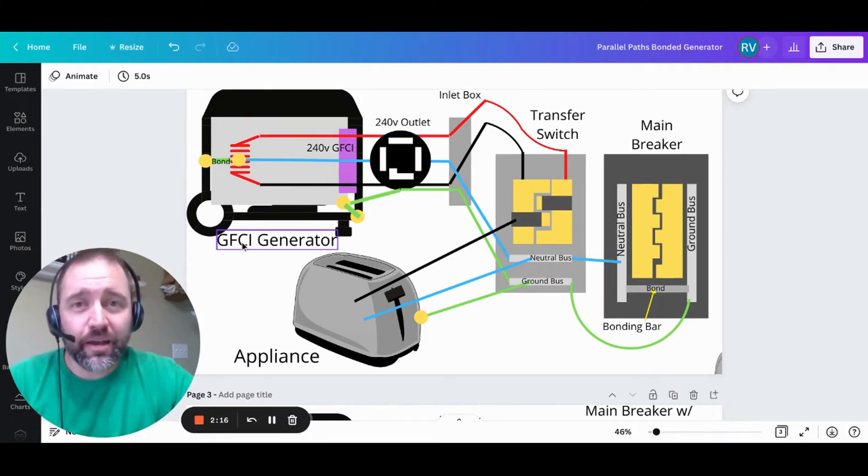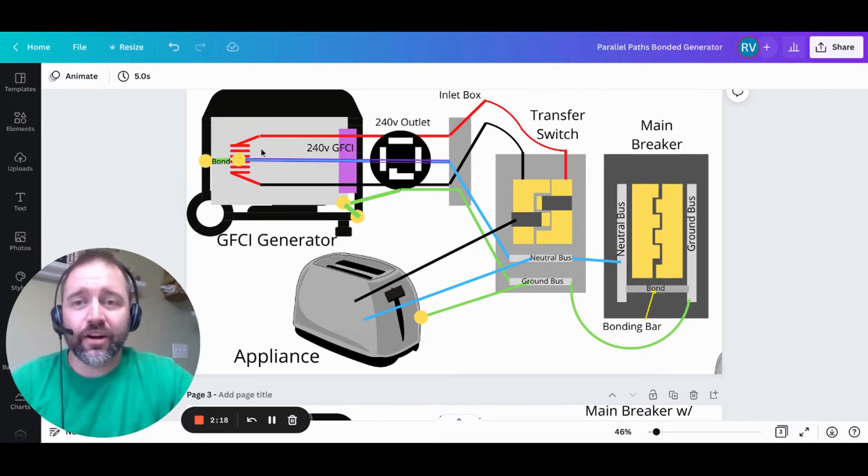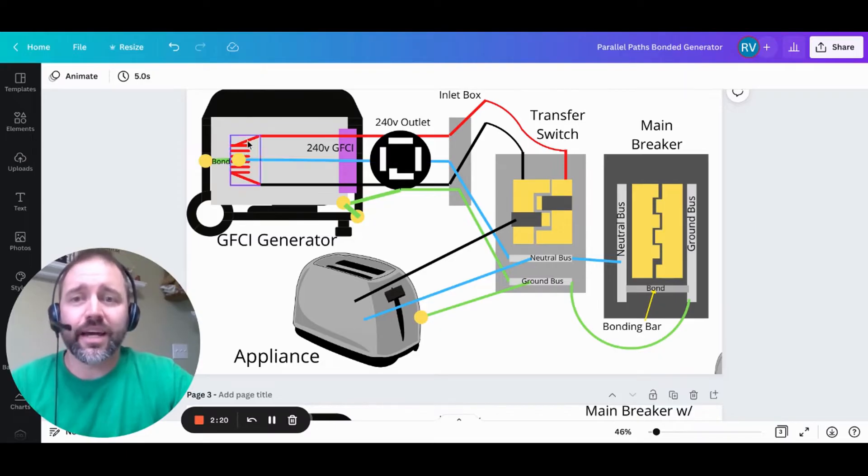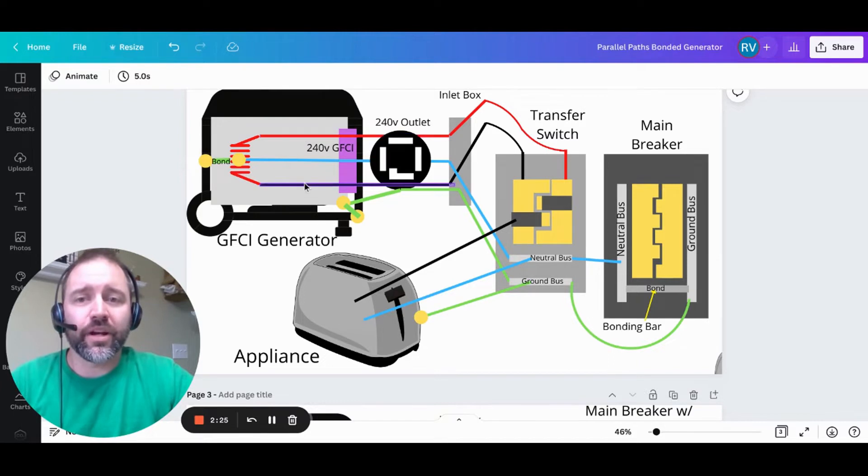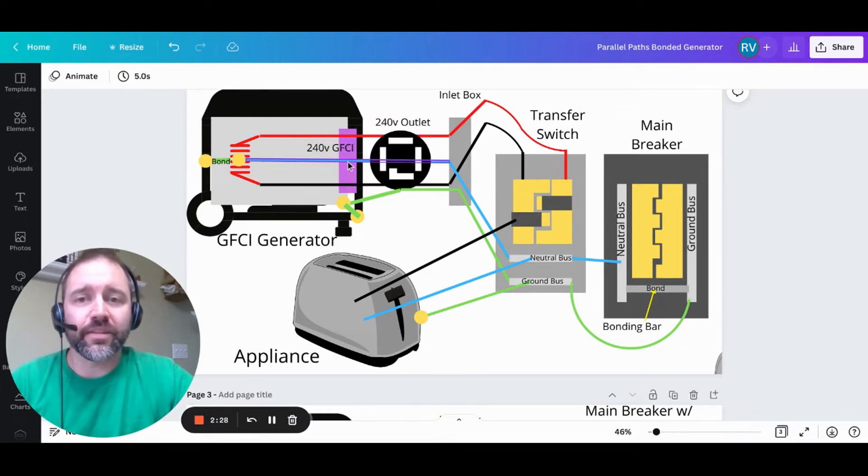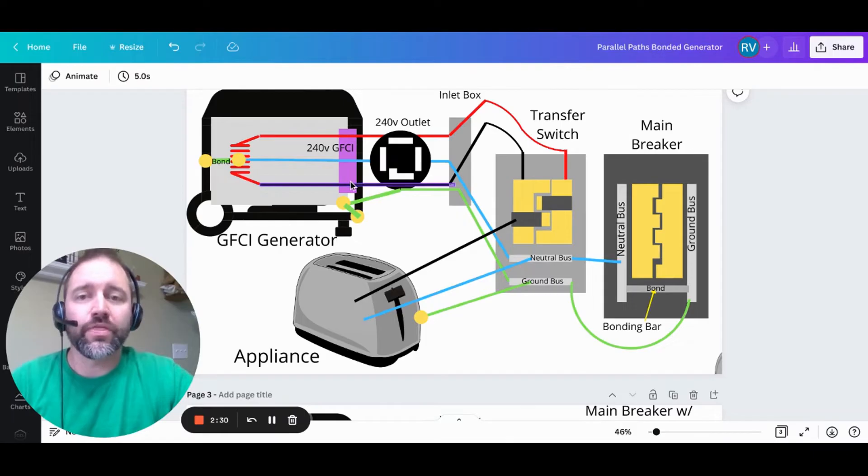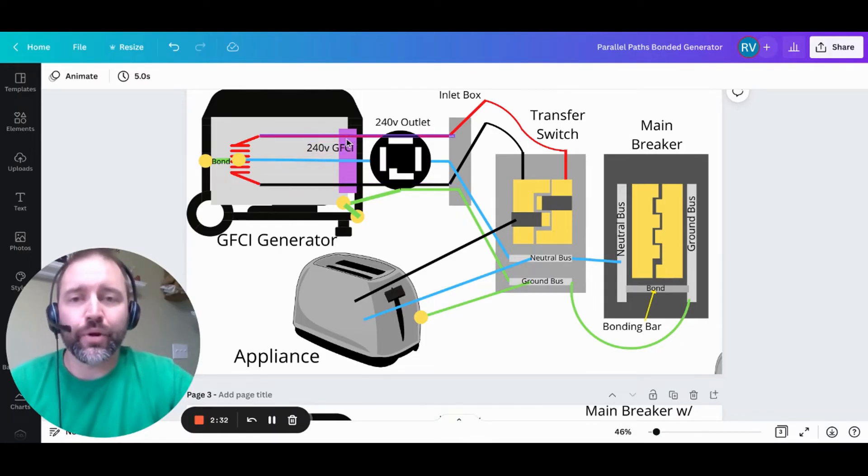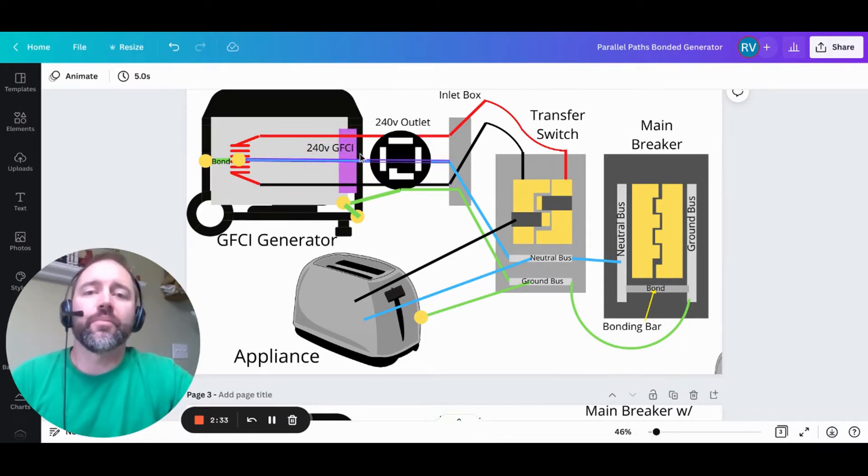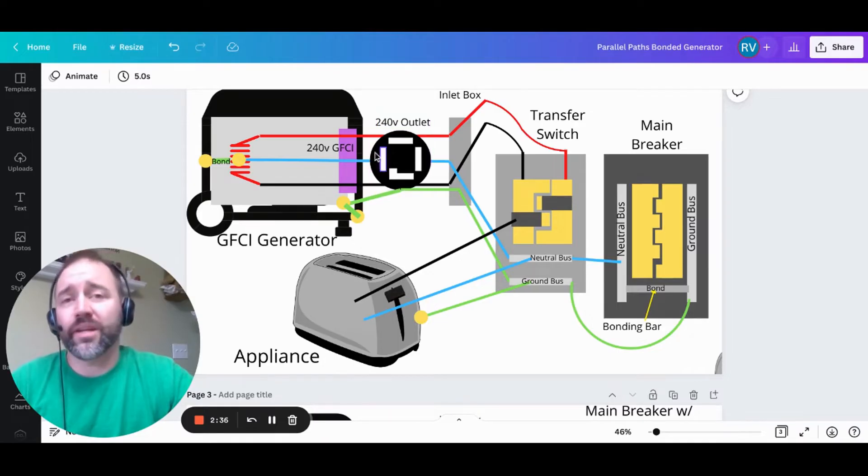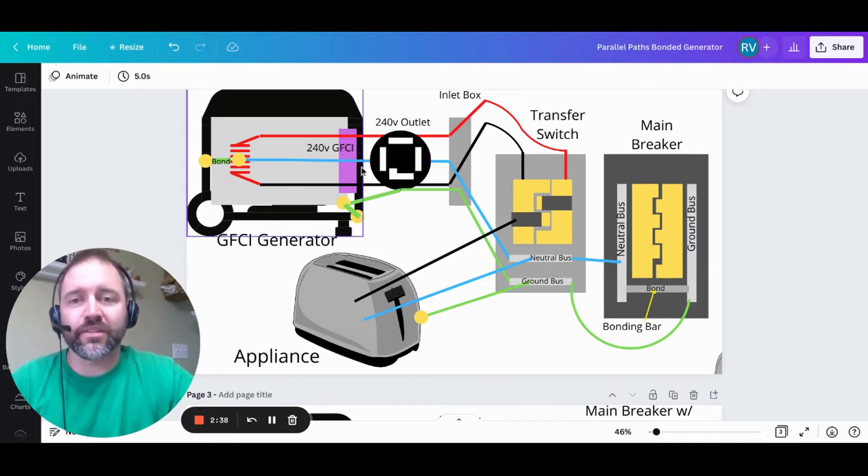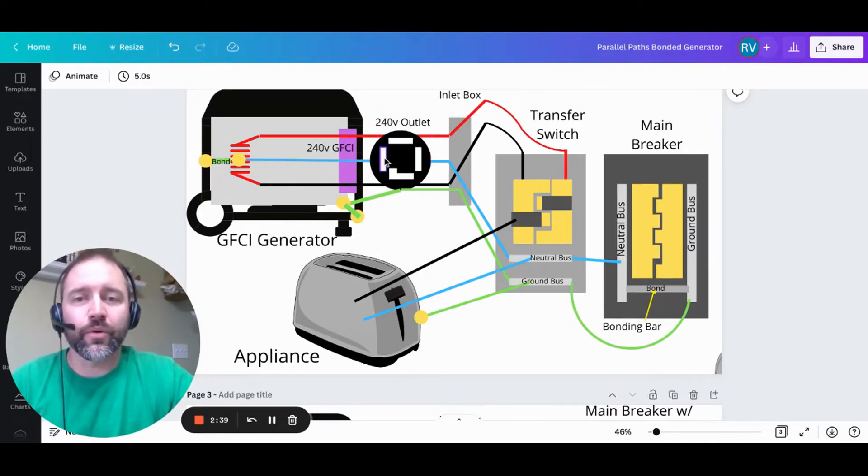So let's get into this. With our GFCI-protected generator, we have our coils here creating our electricity inside. We have 120 volts here, 120 volts here on the black, so one on the red, one on the black, creates 240 volts. With a neutral tapped in the center, these three wires run through your GFCI-protected breaker. From there, it goes to your 240-volt outlet, which would be attached to your generator.